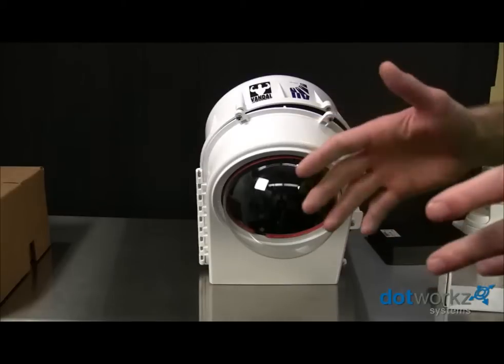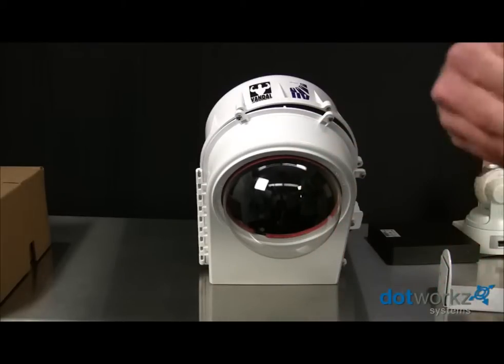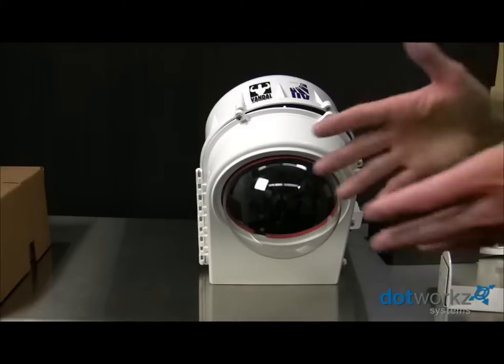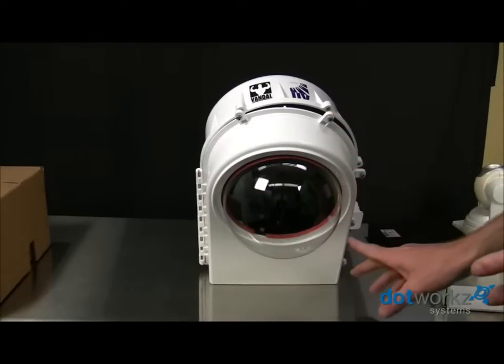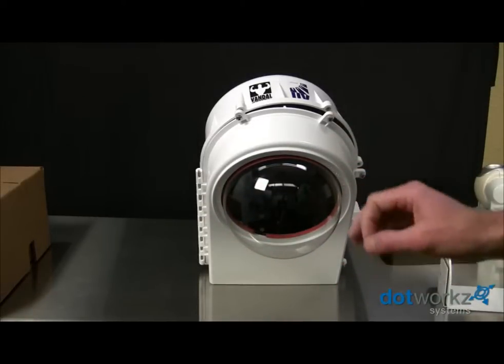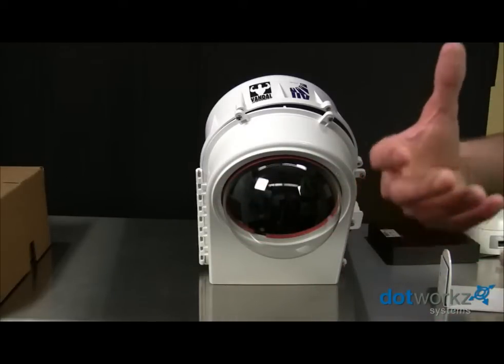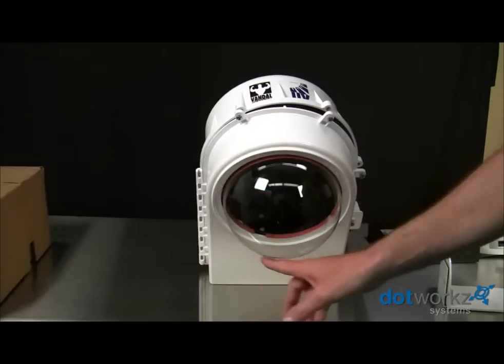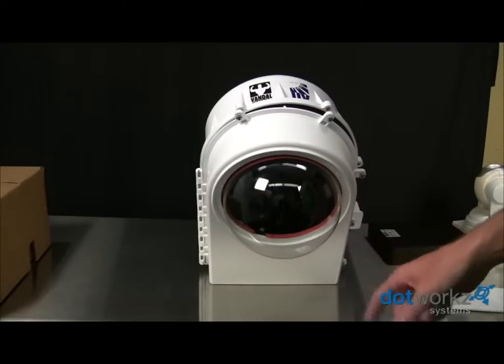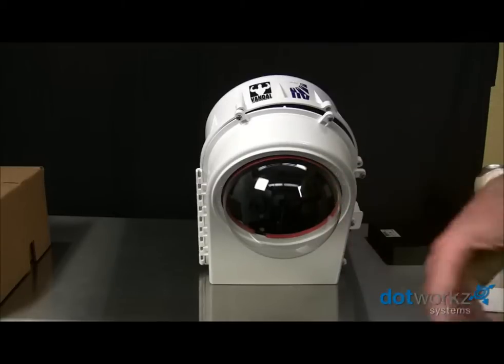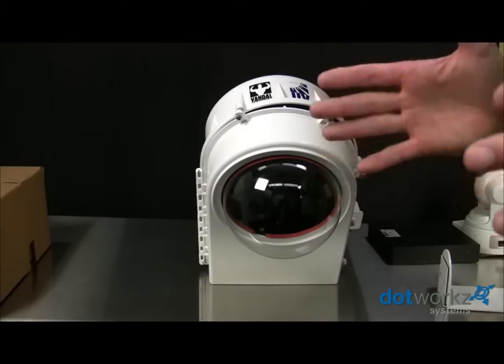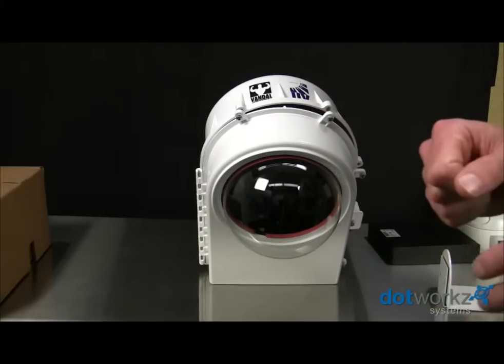this solar version is built specifically for that 12-volt input. That 12-volt input has been stepped down to work with different camera voltages, but also we have put in a very specific and focused heating system as opposed to our bigger, more robust de-icing systems. The smaller, lower-wattage heating solution and the smaller fan combined make up much less of a draw for those types of applications.